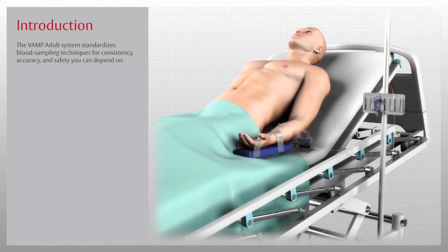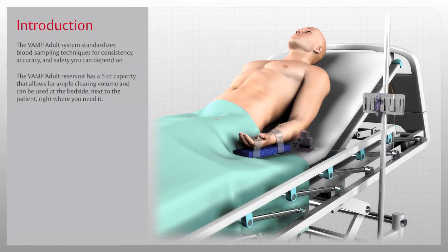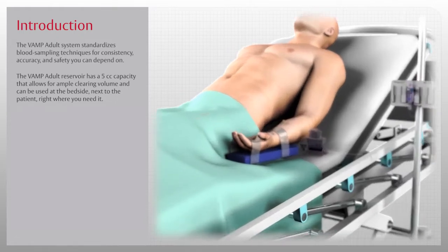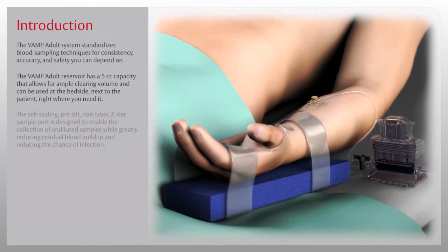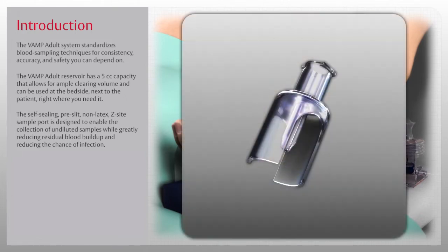Setup, priming, sampling, and flushing are quick and easy with the VAMP Adult System. The VAMP Adult reservoir has a 5 cc capacity that allows for ample clearing volume and can be used at the bedside, next to the patient, right where you need it. The self-sealing, pre-slit, non-latex Z-Site sample port is designed to enable the collection of undiluted samples while greatly reducing residual blood buildup and reducing the chance of infection.